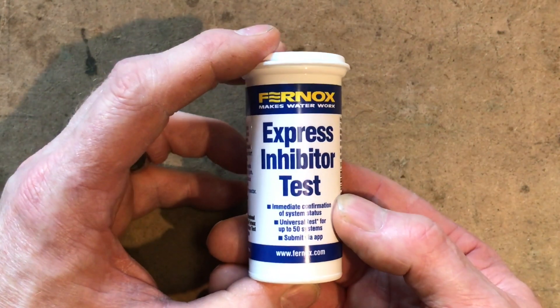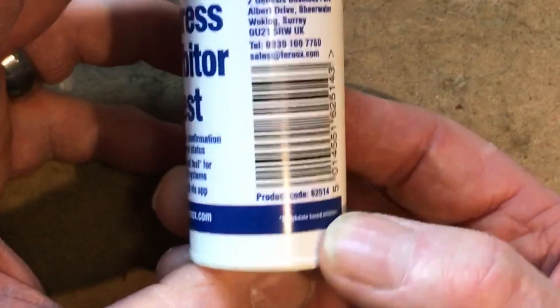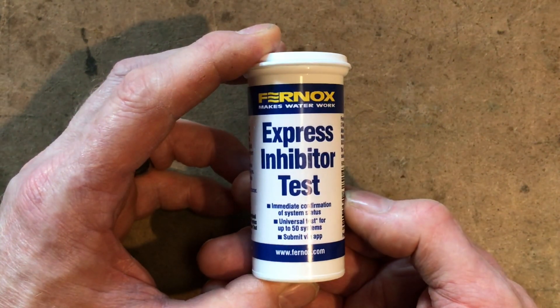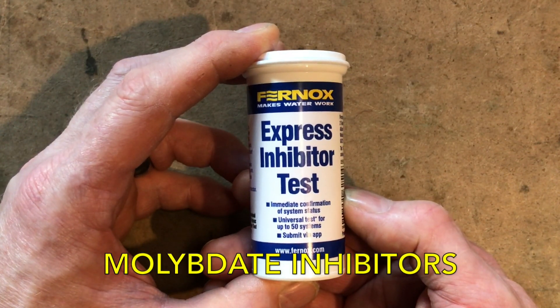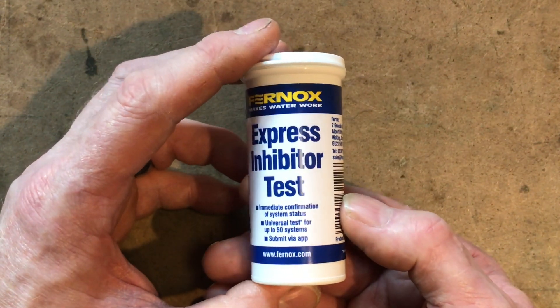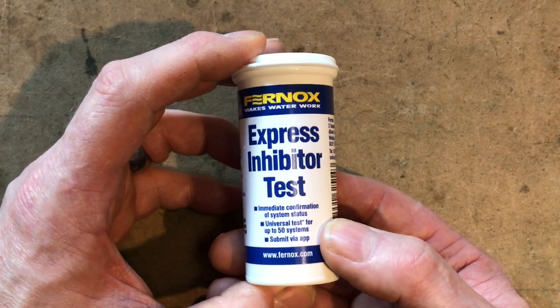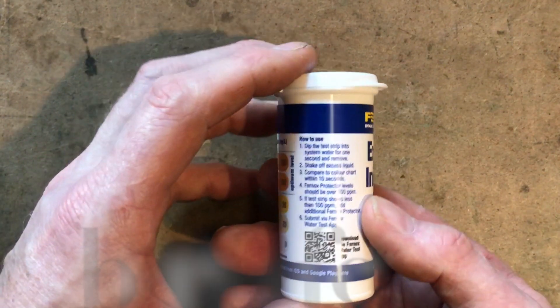So it's the Fernox Express Inhibitor Test Kit, product number 62514. This product tests whether your central heating system has got any inhibitor in it. It will test all Fernox products but it will also test other molybdate-based inhibitors. It's a quick and simple test method to establish the presence of inhibitor within the heating system, testing the inhibitor concentration. It allows compliance with BS 7593:2019, the benchmark scheme, and may also be required by manufacturers.